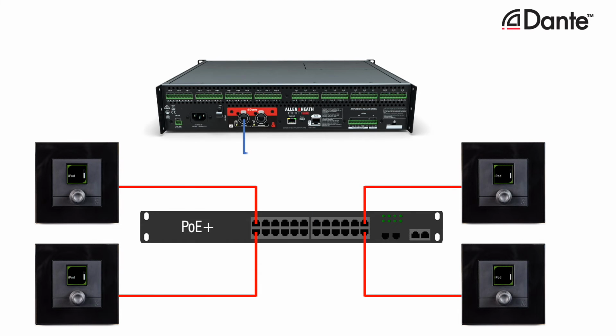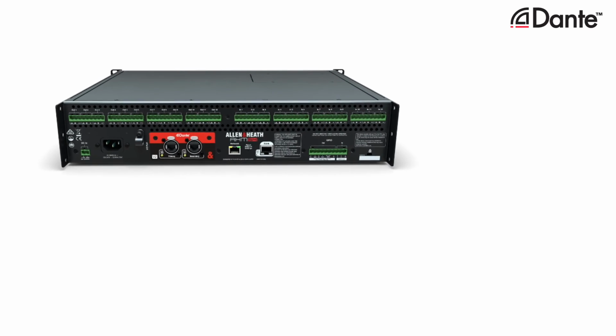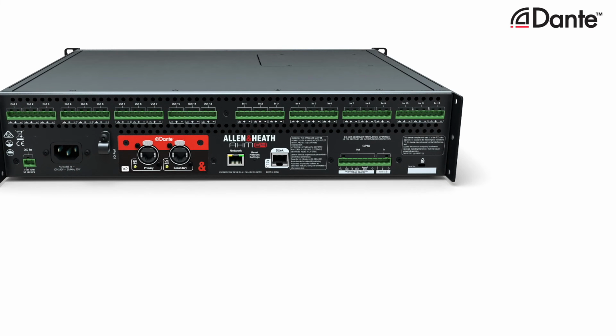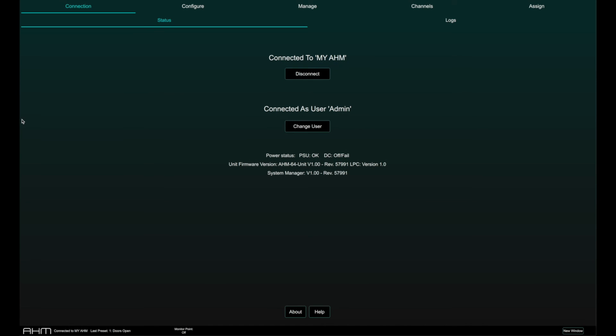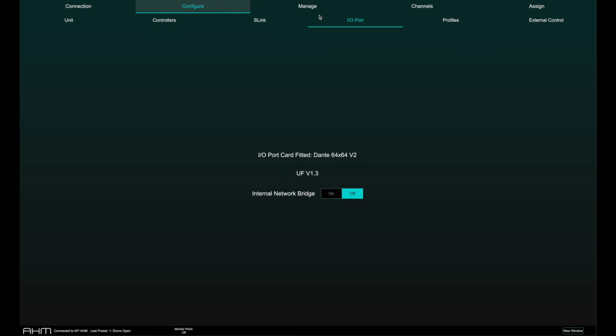IP controllers can also be connected to an AHM Dante network if using the optional Dante card. For this, the internal network bridge must be activated, injecting the AHM remote control network into the Dante network. Activating the internal network bridge is done via AHM System Manager by going to the Configure page, I/O Ports tab, and selecting Internal Network Bridge.